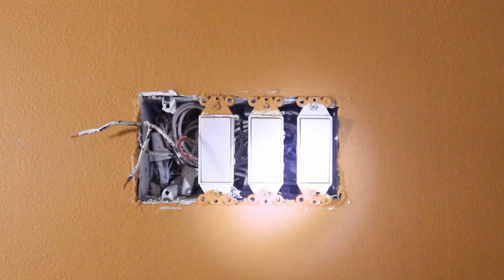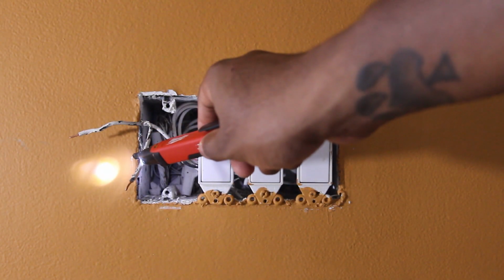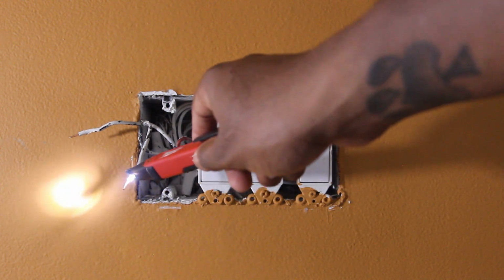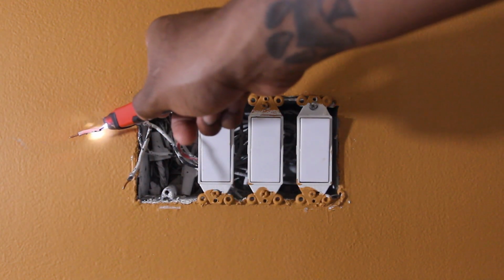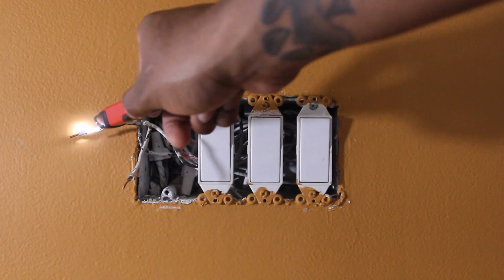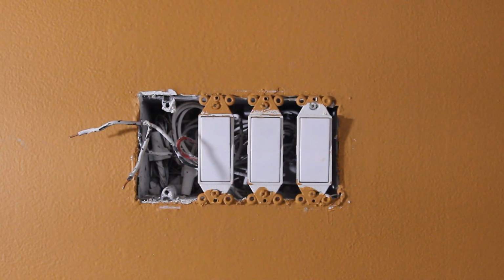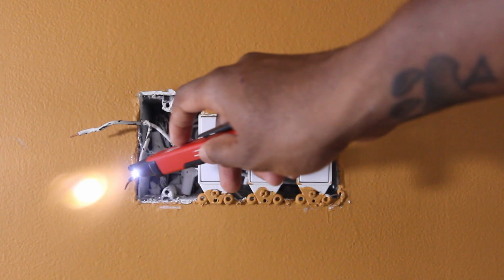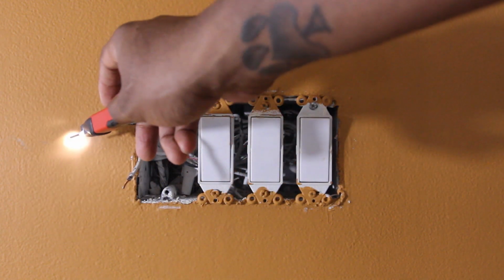Now you have 2 wires exposed, and you can turn the circuit breaker back on to test to see which is your load wire and which is your line wire. The volt detector will give off a beeping sound for your line wire, and nothing for the load wire. Once you find out which is which, be sure to take off the power from the circuit breaker before you touch the wires again.